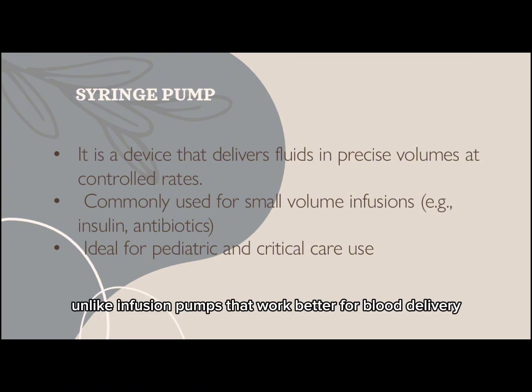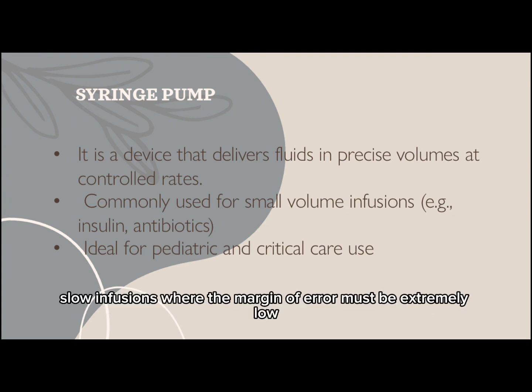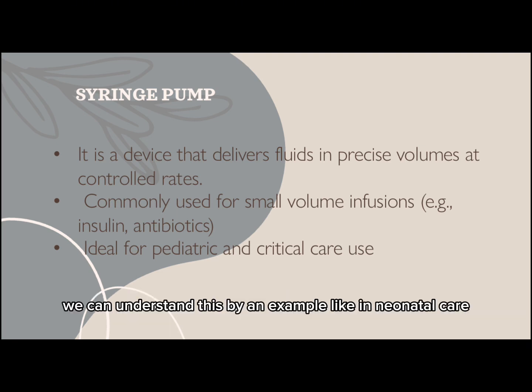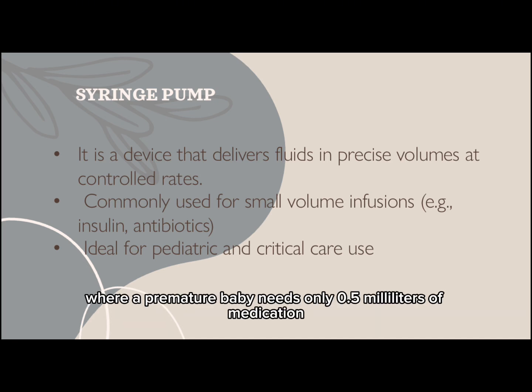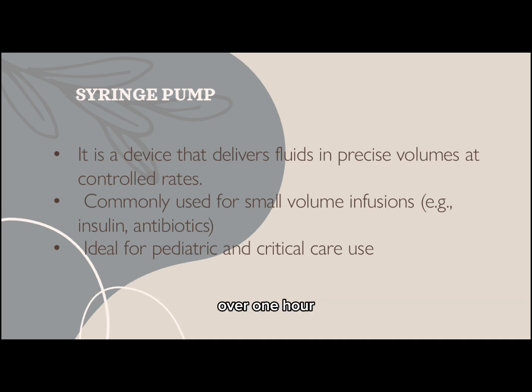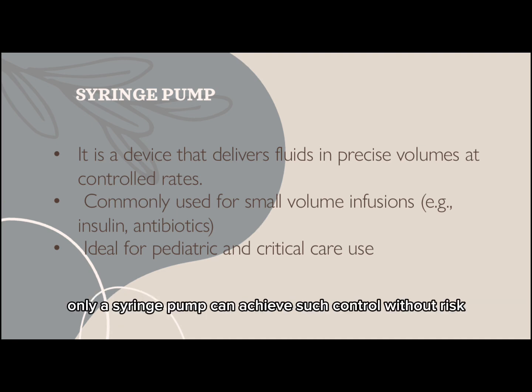Unlike infusion pumps that work better for bulk delivery, syringe pumps are best suited for small volumes, slow infusions where the margin of error must be extremely low. For example, in neonatal care, where a premature baby needs only 0.5 milliliters of medication over 1 hour, only a syringe pump can achieve such control without risk.